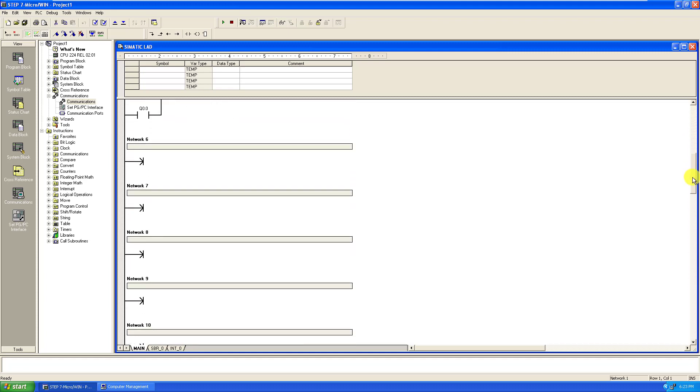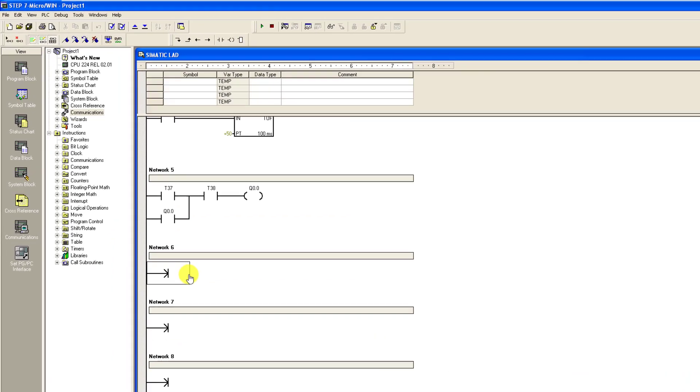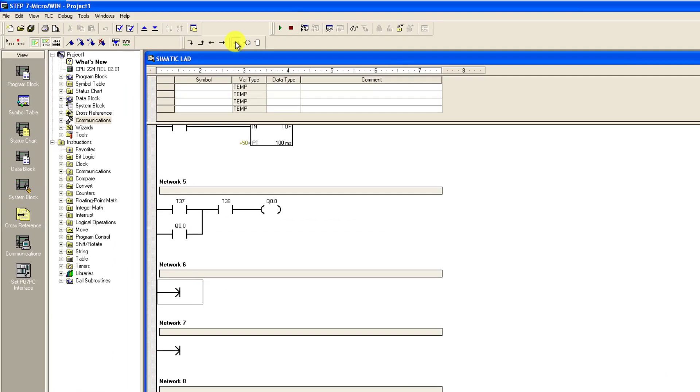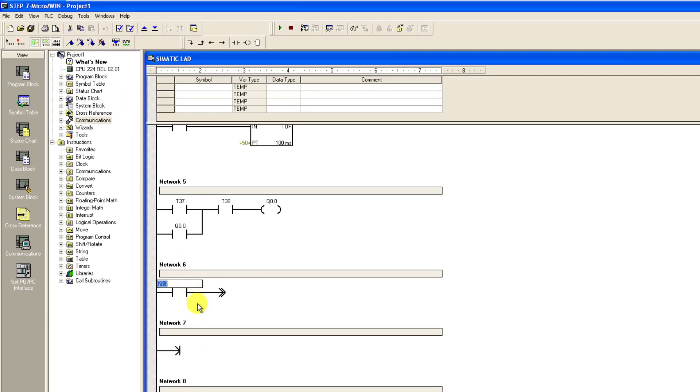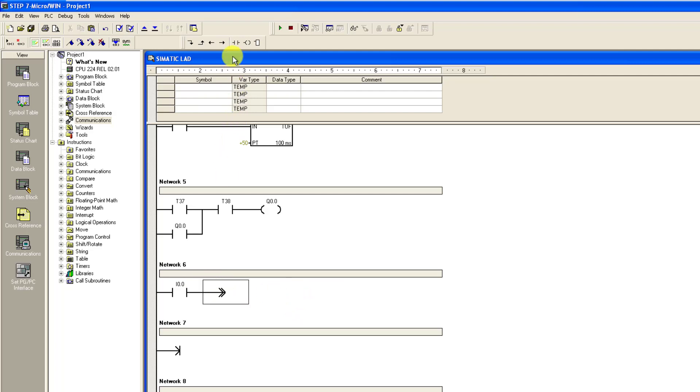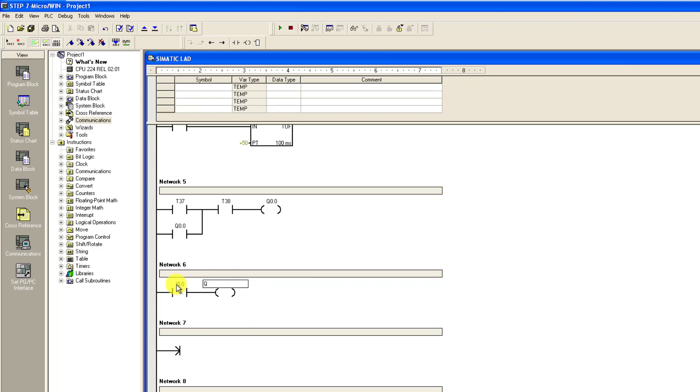We can see that this is the old program in the PLC. Now let's move to network 6 and then add a simple program to test the PLC. So I click on the normally open contact and then label it I0.0. So that whenever I0.0 is activated, the output Q0.7 will come on. So I give it address Q0.7.